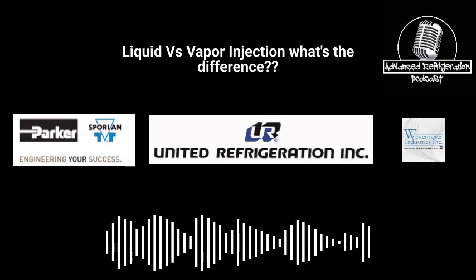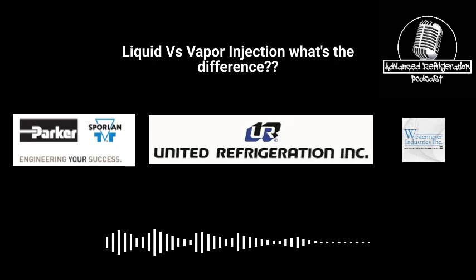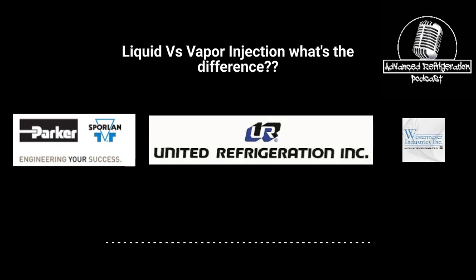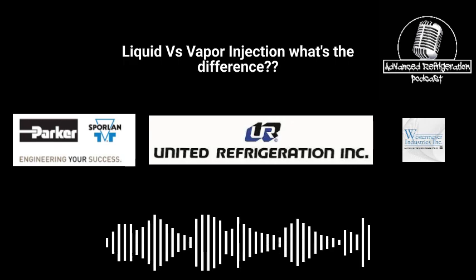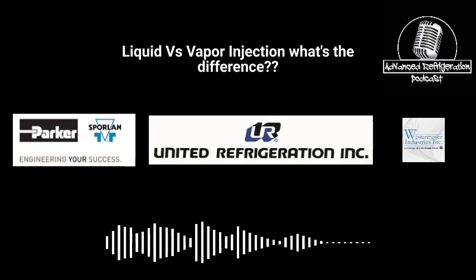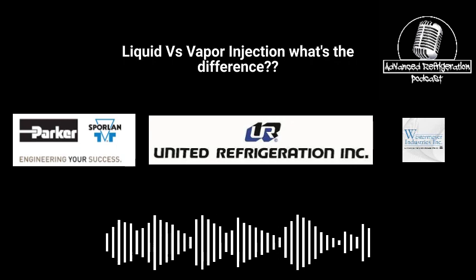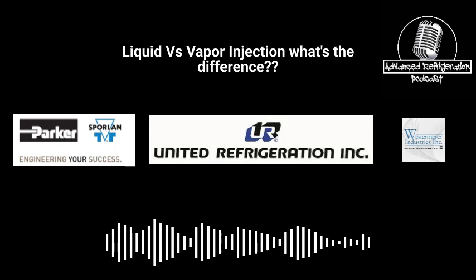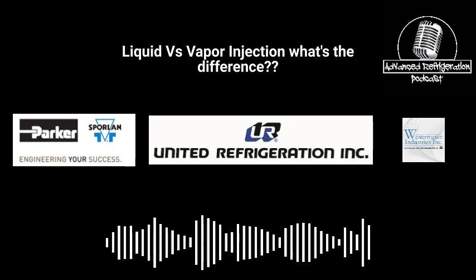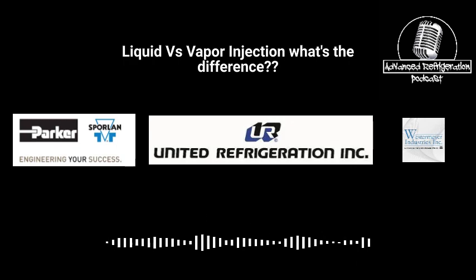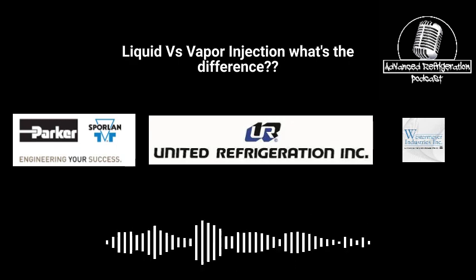Same thing with the DTC valves on the scrolls. Typically on the newer ones, they have a bulb that actually goes in the top of the head of the compressor. If you're replacing a compressor, do not grab that with the channel locks. I've seen on multiple occasions where someone couldn't get it out easily enough, and what they do is squeeze it with the channel locks, which essentially is putting more pressure on the bulb, which is putting more pressure against the spring and essentially causing that thing to feed nonstop, even when it doesn't need to. So I just tap the edges of the DTC valve, the stem. I just kind of tap it with a pair of channel locks on the edges, try to loosen it up, and then PB Blaster. Load it up with PB Blaster and start pushing on it, and that oil, once it gets down underneath, will push the bulb out.